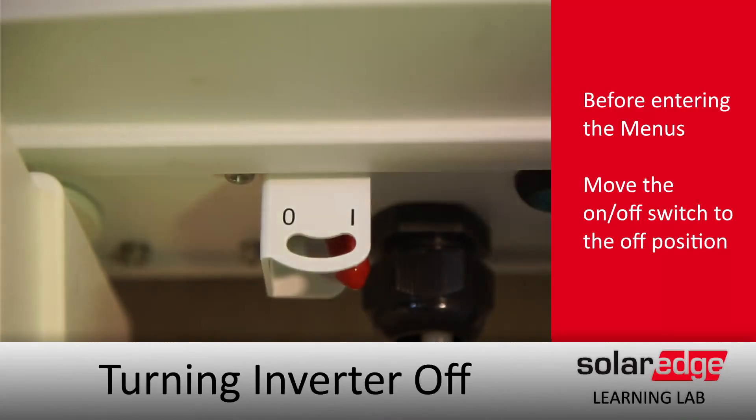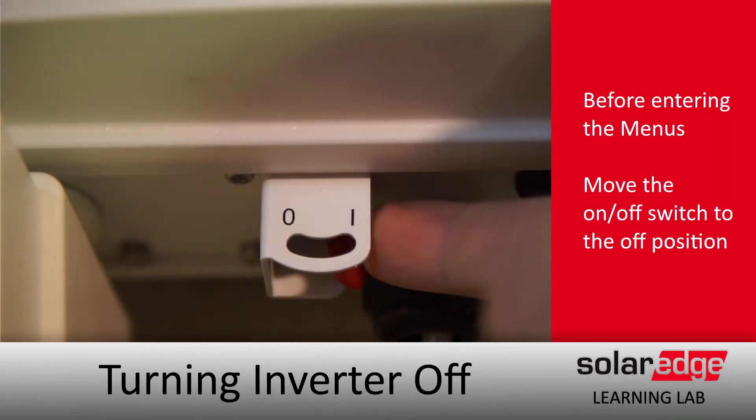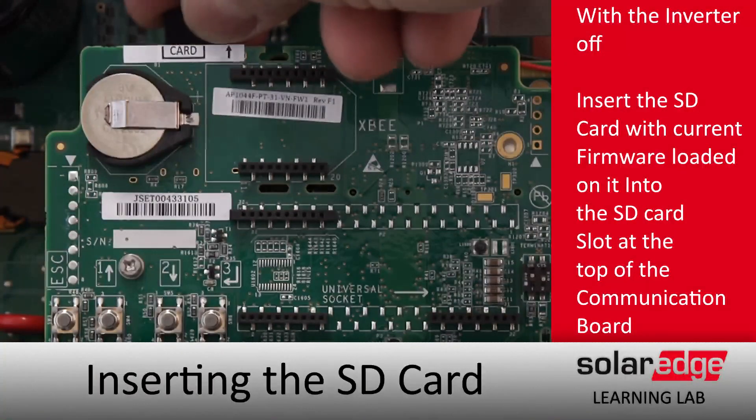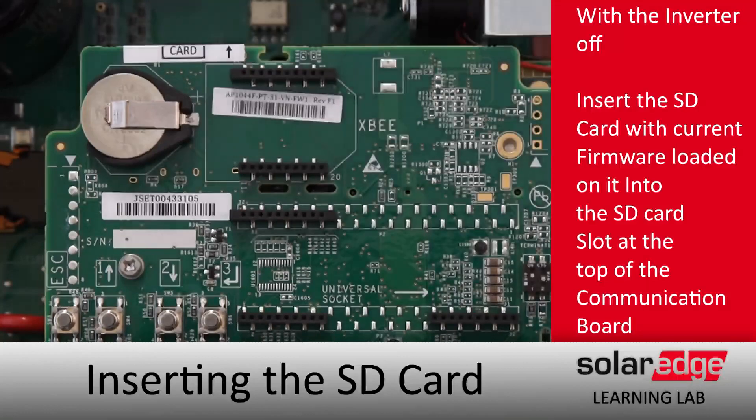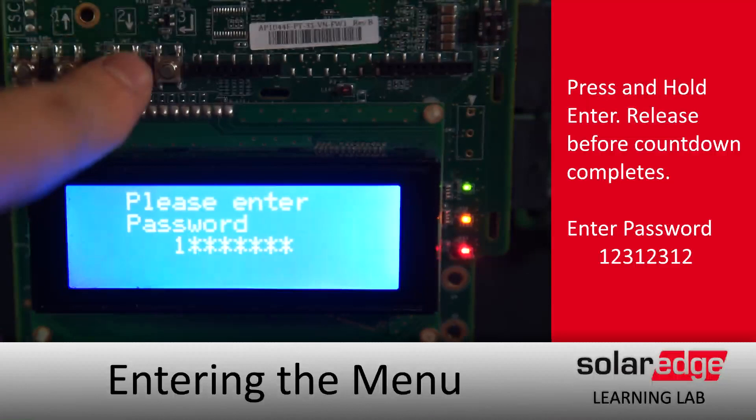To start the firmware update, turn the one-zero toggle to zero and let the DC voltage bleed down to a safe level before opening the cover and popping the micro SD card into the top of the comm board. After that, go into the menus by doing a long hold on Enter and entering the password 1-2-3-1-2-3-1-2.